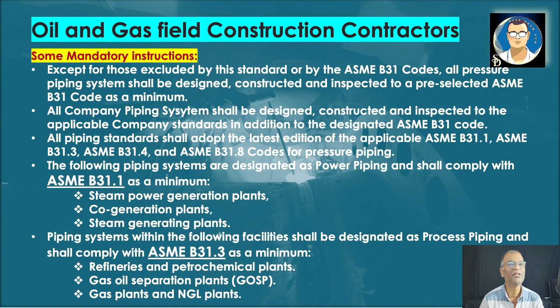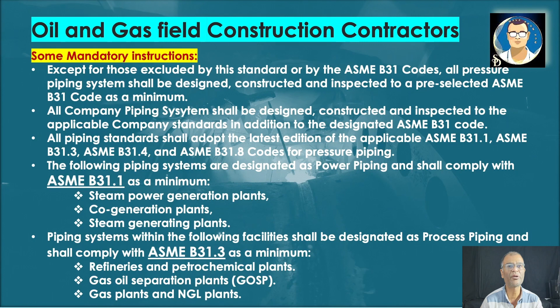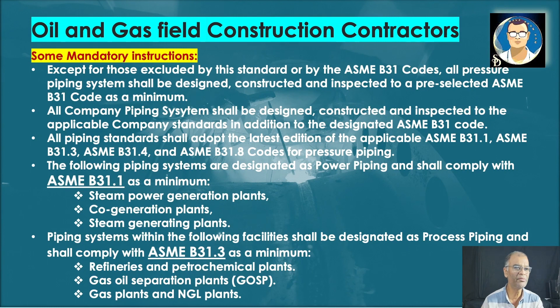In the standards, there are mandatory instructions: all pressure piping systems shall be designed, constructed, and inspected to a pre-selected ASME B31 code as a minimum. Piping standards shall adopt the latest edition of applicable codes: B31.1 for power piping, B31.3 for process piping, and B31.4 and B31.8 for pipeline-related utility piping. Areas following B31.1 include steam power generation plants, co-generation plants, and steam generation plants.